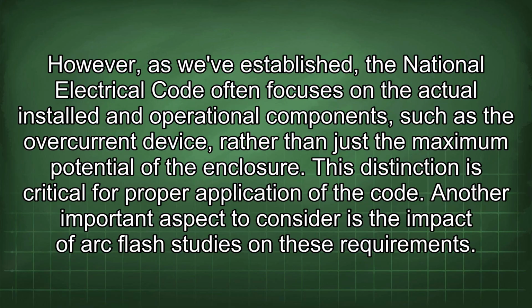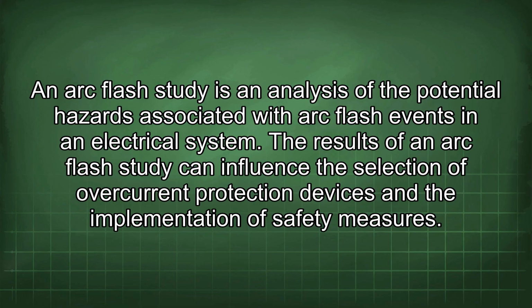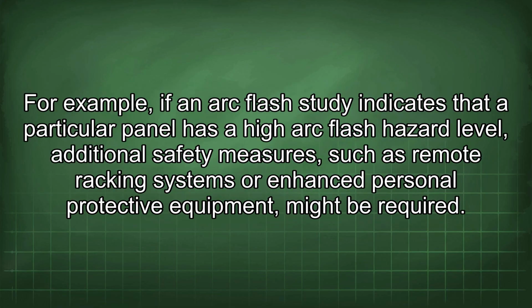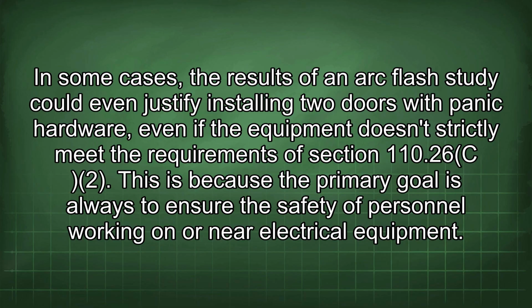Another important aspect to consider is the impact of arc flash studies on these requirements. An arc flash study is an analysis of the potential hazards associated with arc flash events in an electrical system. The results of an arc flash study can influence the selection of overcurrent protection devices and the implementation of safety measures. For example, if an arc flash study indicates that a particular panel has a high arc flash hazard level, additional safety measures such as remote racking systems or enhanced personal protective equipment might be required. In some cases, the results of an arc flash study could even justify installing 2 doors with panic hardware, even if the equipment doesn't strictly meet the requirements of Section 110.26c2. This is because the primary goal is always to ensure the safety of personnel working on or near electrical equipment.